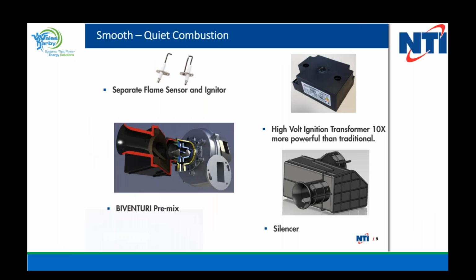Now, we have a very robust flame sensor and igniter. We have also that high voltage transformer you can see there on the top, and on the bottom the silencer. That keeps us running very quiet. So this is a very quiet system.